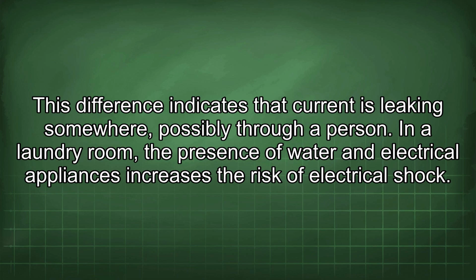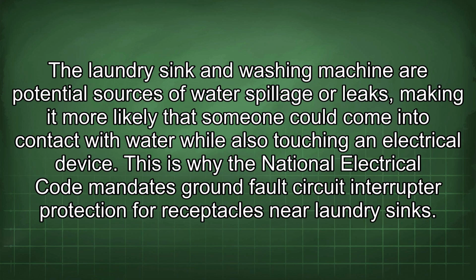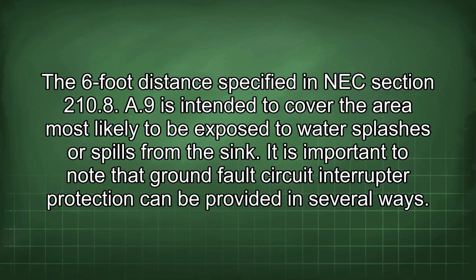In a laundry room, the presence of water and electrical appliances increases the risk of electrical shock. The laundry sink and washing machine are potential sources of water spillage or leaks, making it more likely that someone could come into contact with water while also touching an electrical device. This is why the National Electrical Code mandates ground fault circuit interrupter protection for receptacles near laundry sinks. The 6-foot distance specified in NEC Section 210.8(A)(9) is intended to cover the area most likely to be exposed to water splashes or spills from the sink.